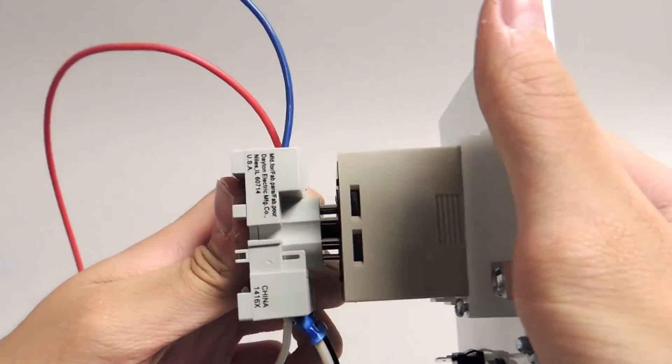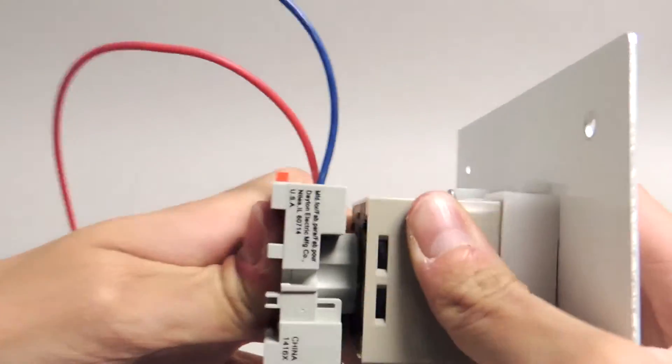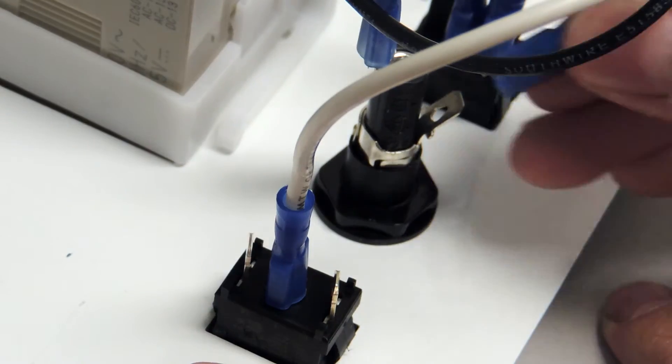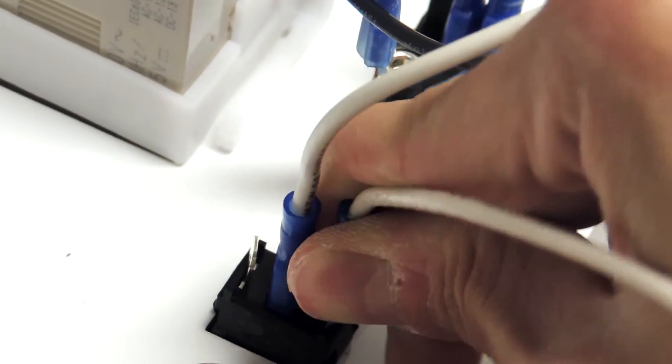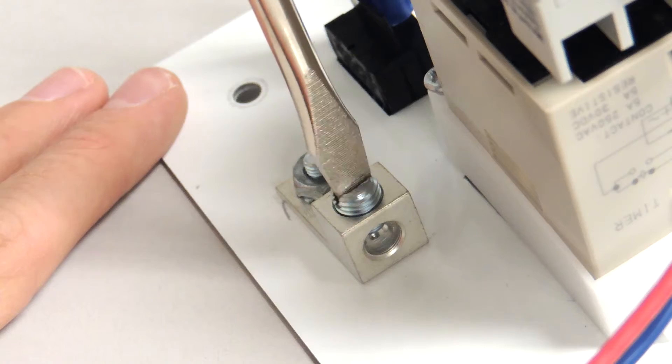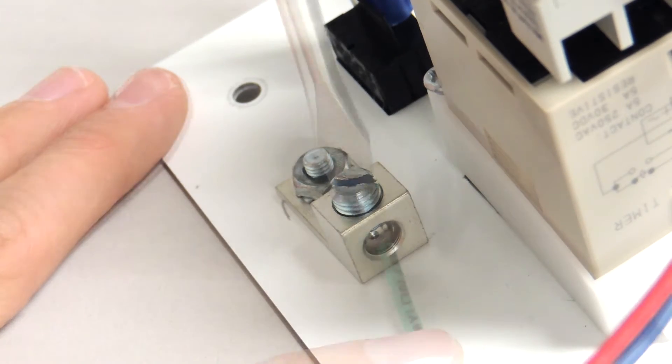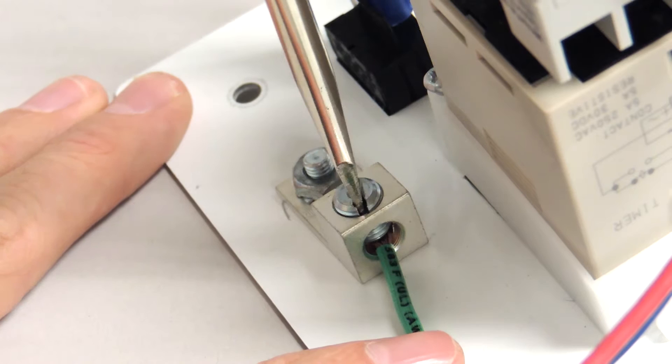Then, reattach the relay backing to the OMRON timer. Now, connect power to the exposed male connector of the fuse and to the bottom prong on the manual purge switch. Connect the green wire end to the ground screw on the timer unit.